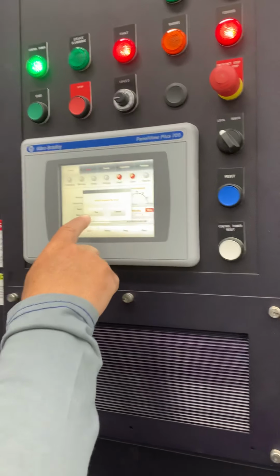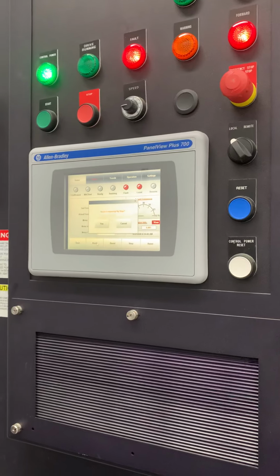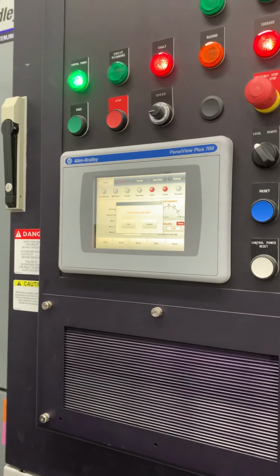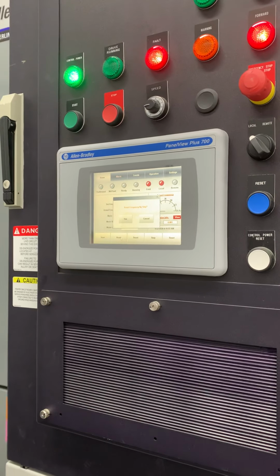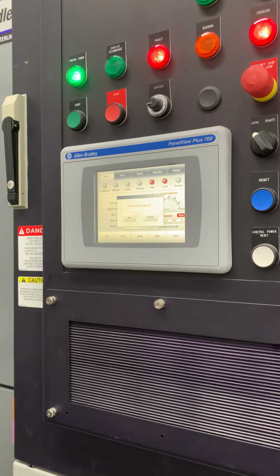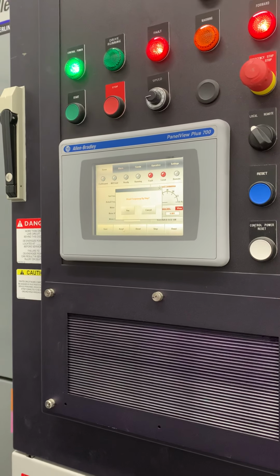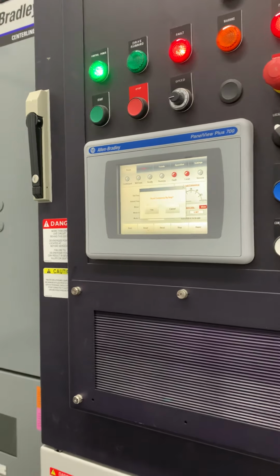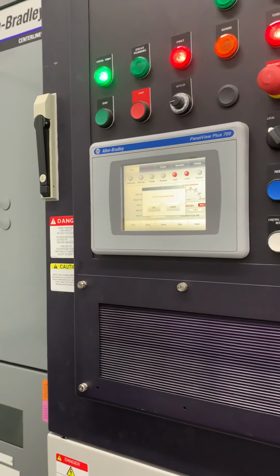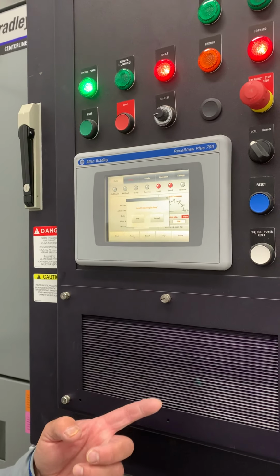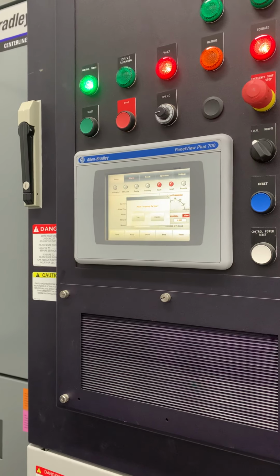Well, no, this is Accel frequency by step. So there's certain steps you can set in there. If you have an application where you want it to go to a frequency, and then step up to the next one, and then up to the next one, it's just a stepping. Then you would enable that. But if you don't, like what we're doing, it's just the nice S curve.